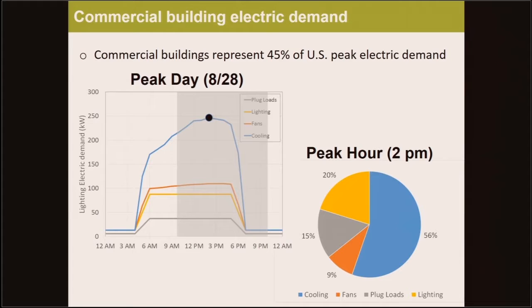Commercial buildings represent nearly half of the U.S.'s peak electrical demand. But what is that demand comprised of? To help answer that question, I developed a simple energy model using eQuest of a typical office building in St. Louis. It's 50,000 square feet, built to the IECC 2009 code, and uses packaged variable air volume systems. I wanted to illustrate how its electric demand varies over a typical day and by end use.